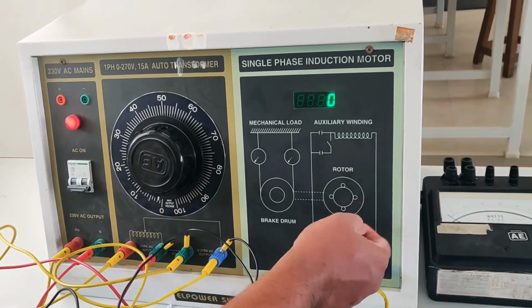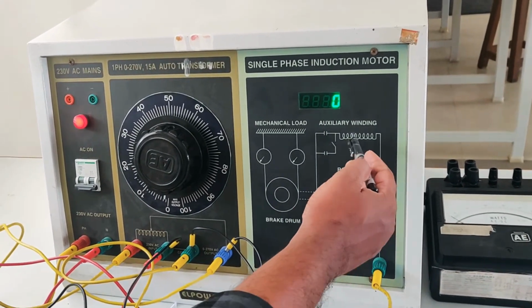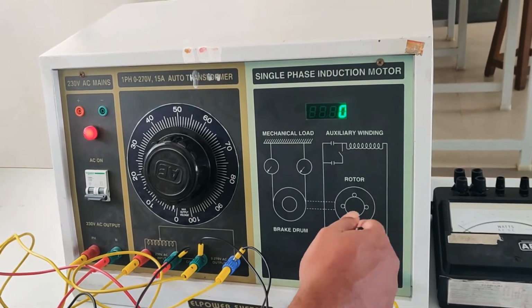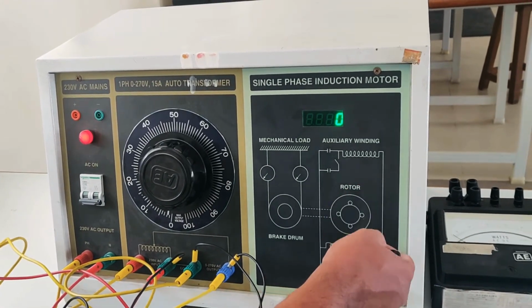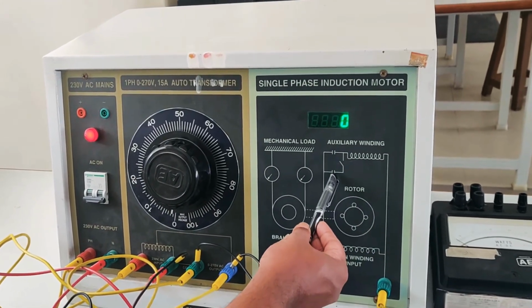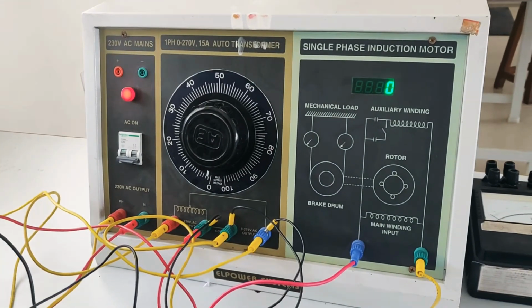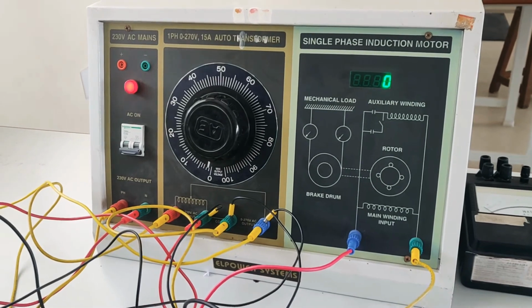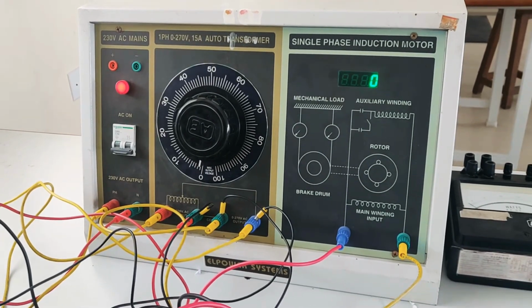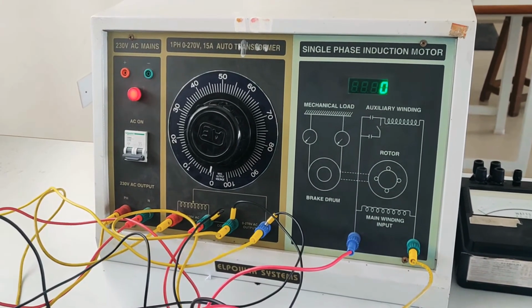This connection is internally done. There is no need to connect the auxiliary winding and main winding in parallel externally. Internally they are connected. This is the starting capacitor, this is the running capacitor. So first you have to understand the main objective of conducting the no load test, and then we shall come to the short circuit test.